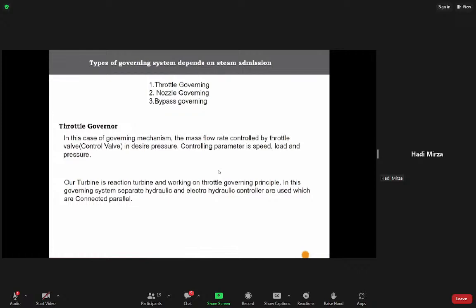The types of governing system depend on the steam admission, basically the valve design. Throttle governing is there. Our 600 megawatt or 250 megawatt units basically work on this throttle governing. In this governing mechanism, mass flow rate is controlled by throttle valves at the desired pressure. Controlling parameters are speed, load, and pressure. Basically, it takes speed, load, and pressure as input and gives the control valve opening as output.